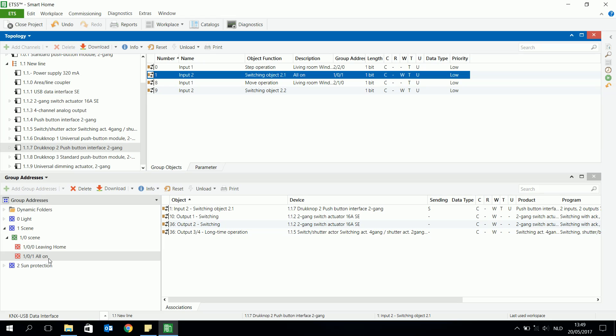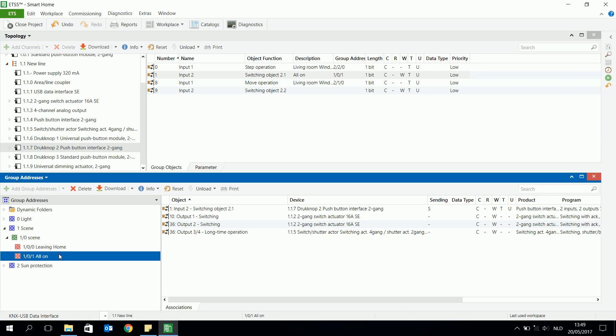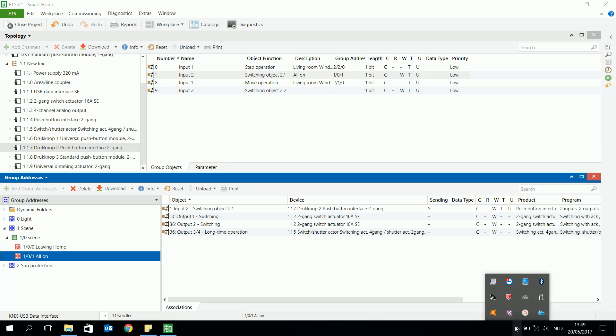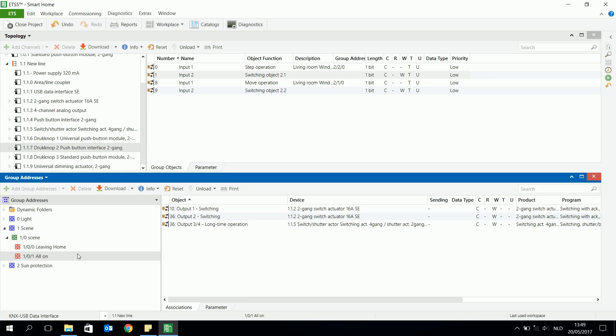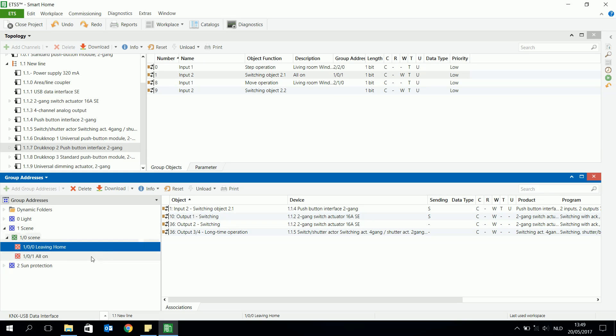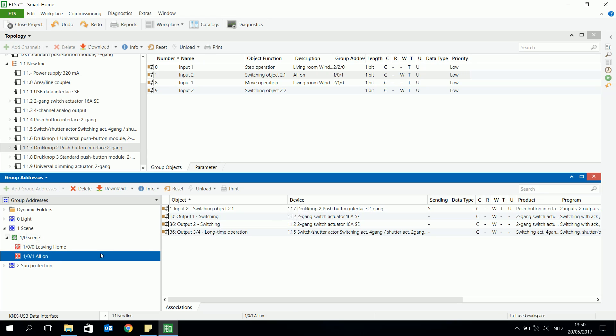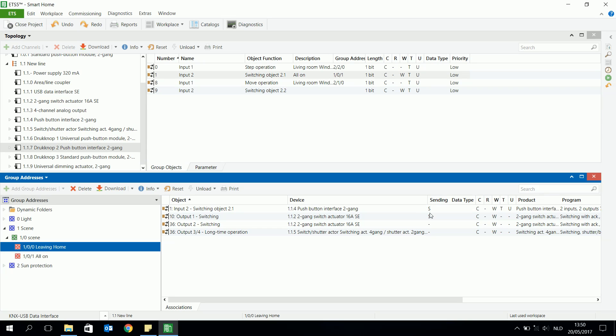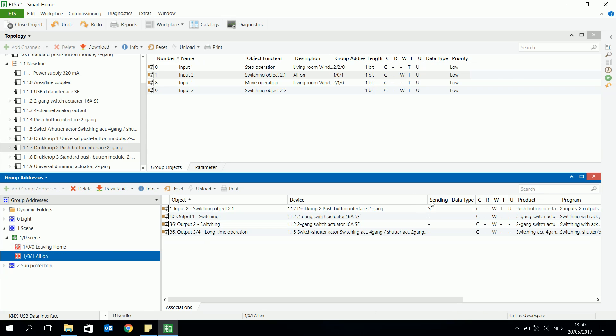You can also just use one group address instead of two different group addresses. I noticed I used the same input twice, so I checked — it's okay because it was a different device. It has the same input two, switching object 2.1, and I was just checking if the S sending flag was still there. In both group addresses the S is still there, so there is no problem — both will be sending in the group address.